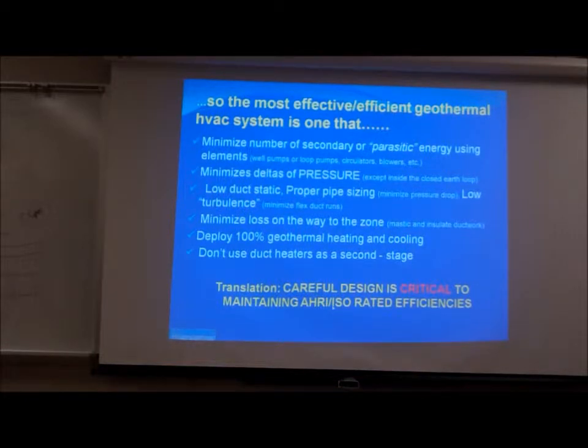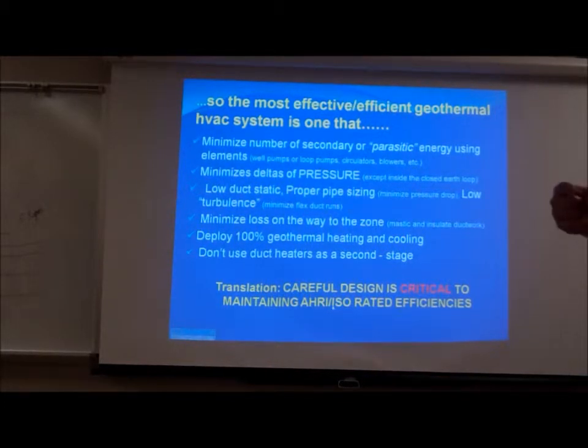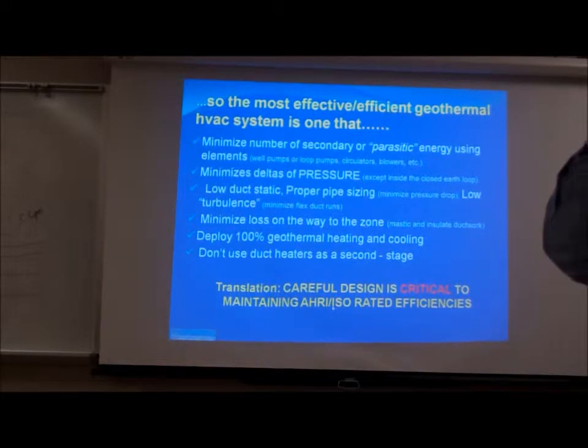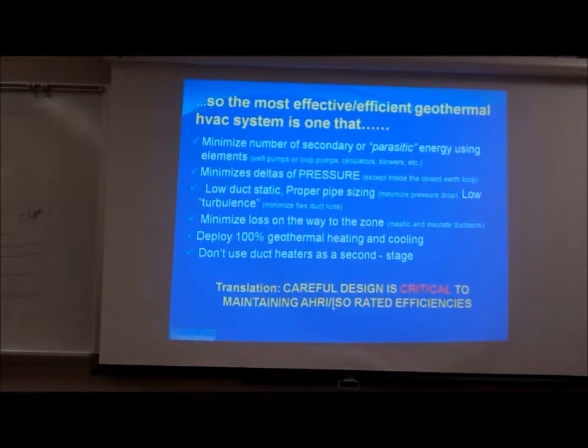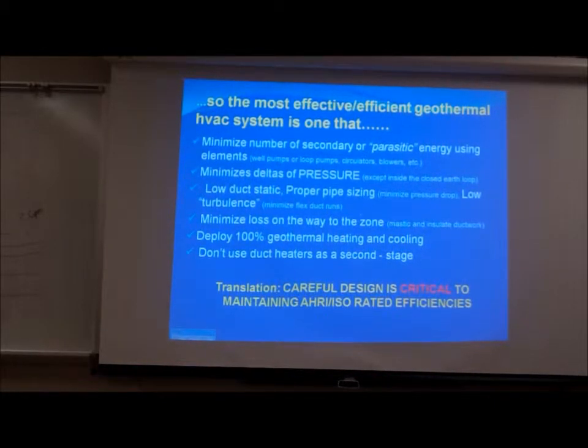With a device that's 500% efficient, when I make mistakes and depart from those laboratory settings by which that unit was identified as efficient, you can multiply those mistakes times 5. I can end up with a COP of 2.5 pretty quick out of a 5 COP device if I don't manage those near-laboratory settings by which the unit got its rating. So minimize the deltas of pressure, except in a closed loop — we'll talk about that in a minute.